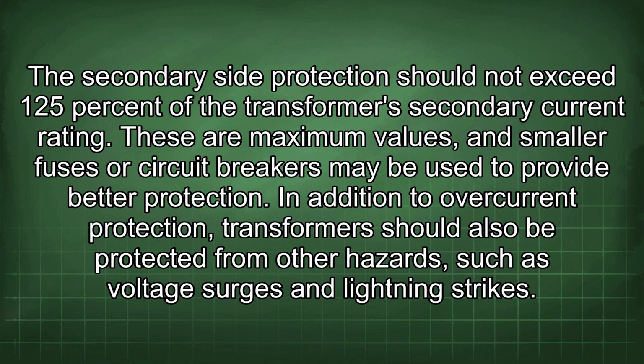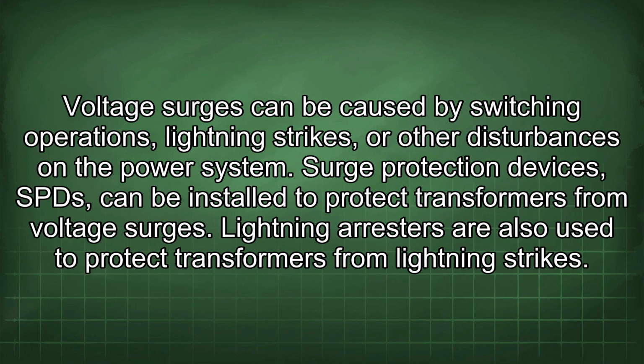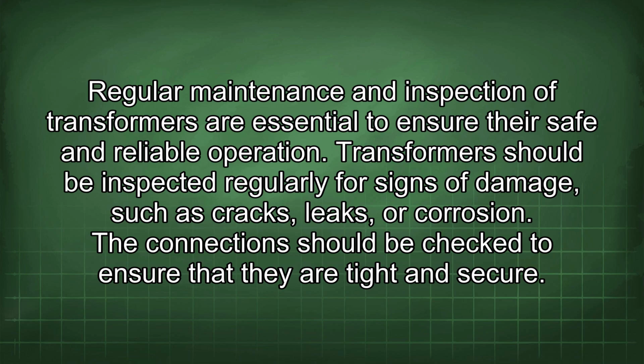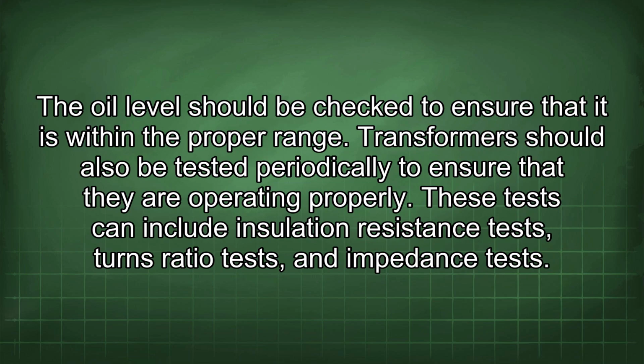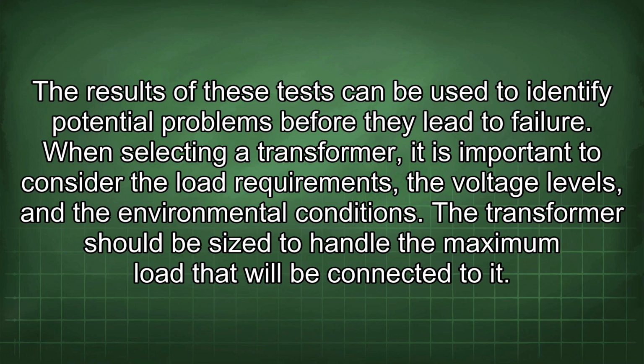In addition to overcurrent protection, transformers should also be protected from other hazards, such as voltage surges and lightning strikes. Voltage surges can be caused by switching operations, lightning strikes, or other disturbances in the power system. Surge protection devices, SPDs, can be installed to protect transformers from voltage surges. Lightning arresters are also used to protect transformers from lightning strikes. Regular maintenance and inspection of transformers are essential to ensure safe and reliable operation. Transformers should be inspected regularly for signs of damage, such as cracks, leaks, or corrosion. The connections should be checked to ensure that they are tight and secure. The oil level should be checked to ensure that it is within the proper range. Transformers should also be tested periodically to ensure that they are operating properly. These tests can include insulation resistance tests, turns ratio tests, and impedance tests. The results of these tests can be used to identify potential problems before they lead to failure.